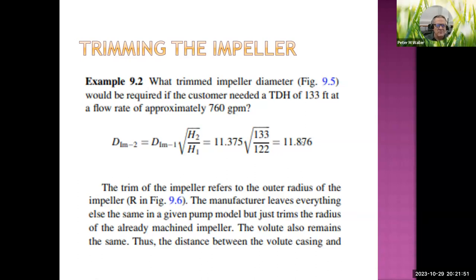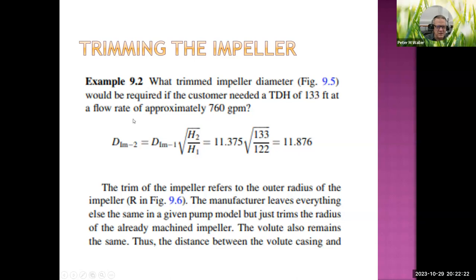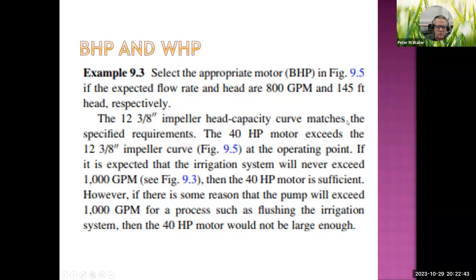In practice you'd just tell the pump company your required flow rate and pressure and they'd trim the impeller. But as a calculation example: for a total dynamic head of 133 feet and 760 gallons per minute, we calculate the trimmed diameter as 11-and-3/8 inches × √(133/122) = 11.876 inches. That's the impeller size you'd specify to the manufacturer.